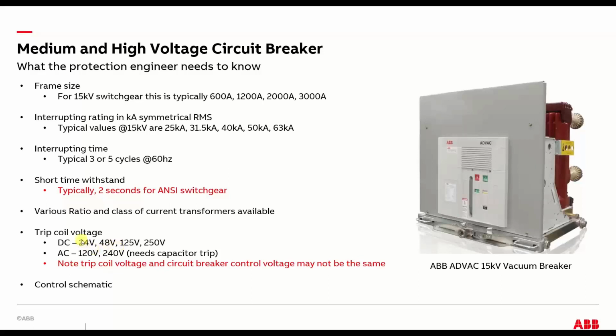And then you should also know what the actual trip coil voltage of the breaker is. Note that the trip coil voltage doesn't have to be the same voltage as any other control in the circuit breaker, like the spring charging mechanism. For example, you tend to want to do your trip coils at DC. So you might have a 48 volt DC trip coil, but then the rest of the system that charges the spring charging motor and does your control and contacts, some of that might be 120 volt AC. So you can easily have mixed voltages in a circuit breaker. It's just something you need to be aware of.